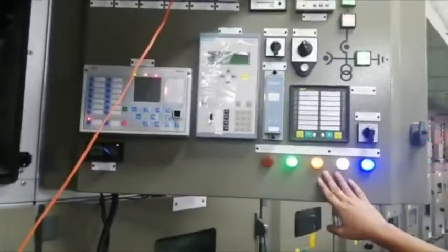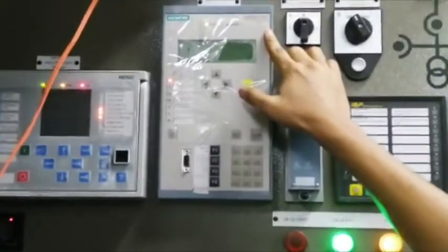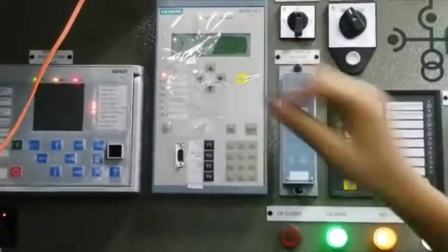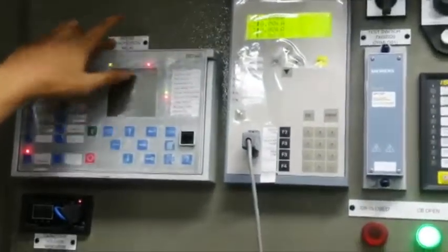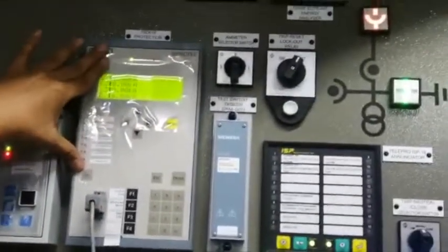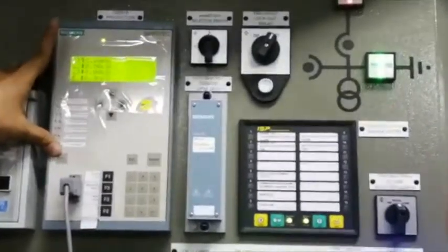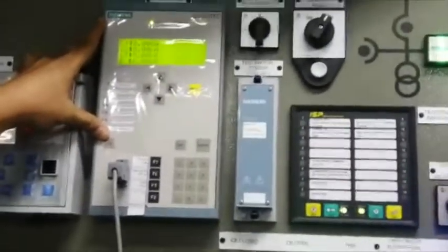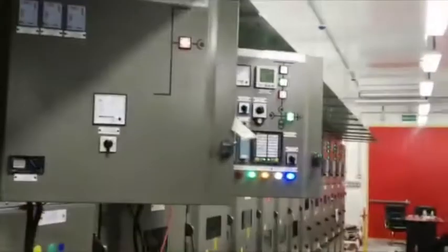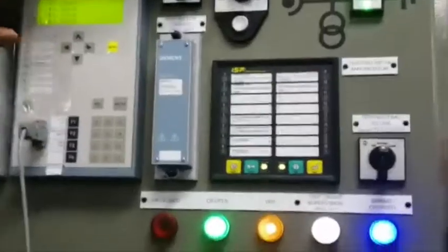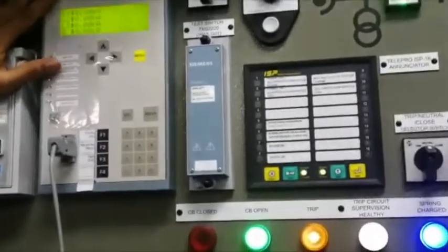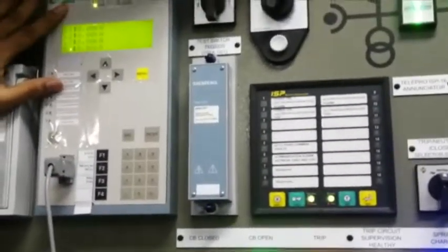In this switchgear, I am going to test 7SD6101 relay. This is our first incomer. In this feeder, we have ABB relay. For ABB relay, main 1, this one is main 2. This will see the differential protection. Here only we have 11 kV relay, so I am considering that second incomer as a 132 kV relay first. Our 11 kV side CT ratio is 3150 amps and our HV side 400 amps.